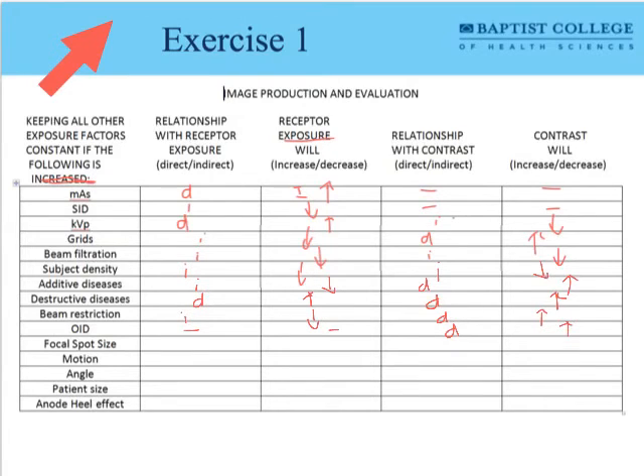Focal spot size is best thought of as a geometrical factor. It really has no relationship to density — if I had the exact same mAs and changed my focal spot size, I should get the same receptor exposure if the machine is appropriately calibrated. It doesn't have an effect on contrast either. It's essentially null across the board as a geometrical factor.